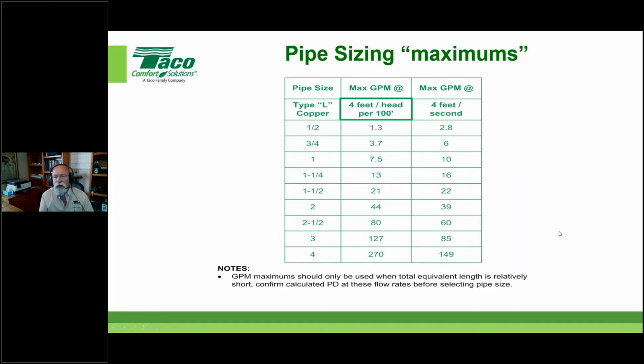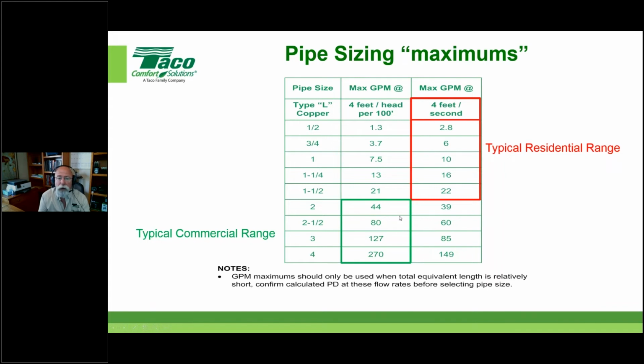And just again, since this is review, a lot of you folks have seen this before, but the idea is doing the right pipe size helps quite a bit, especially in overall pressure drop and things like that. Remember that typically down to 1.5 inches covers us up to most residential applications, and starting at 2-inch and bigger would cover most of our commercial range, right? So notice one thing that's significant about these maximums. Right where the colors change here from green to red, and residential goes to commercial, it also flip-flops in the amount. Notice this column gives you more flow than this column until you get to 2-inch, and then this column gives you more flow capacity than this column does. So you guys that are out there doing work that kind of goes into commercial, just remember where you can flip-flop to your advantage, okay?